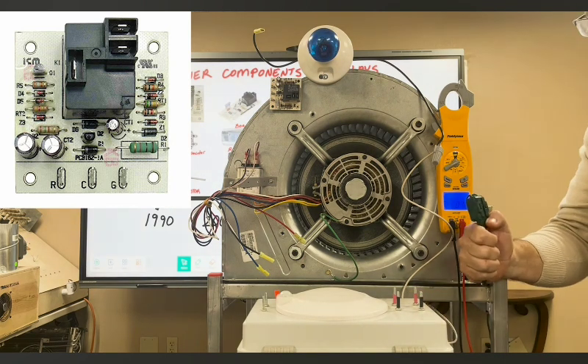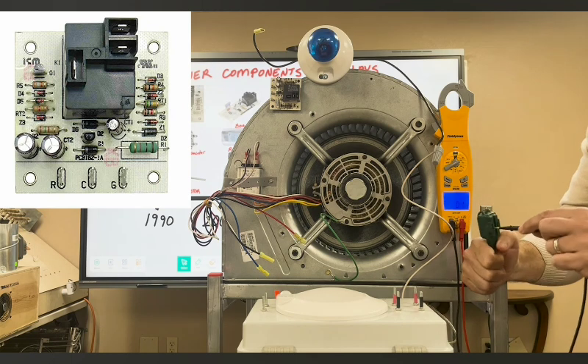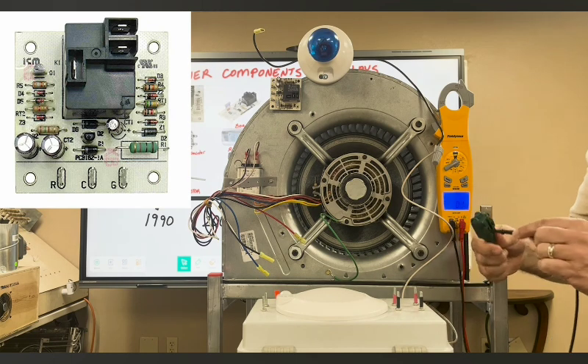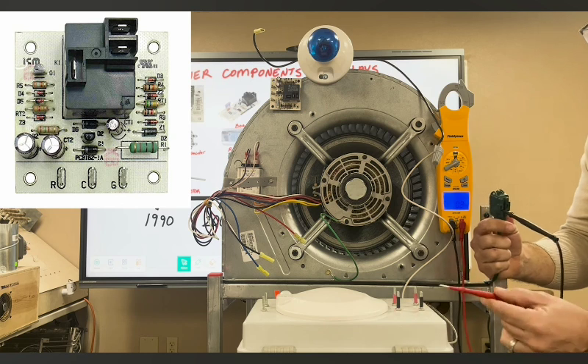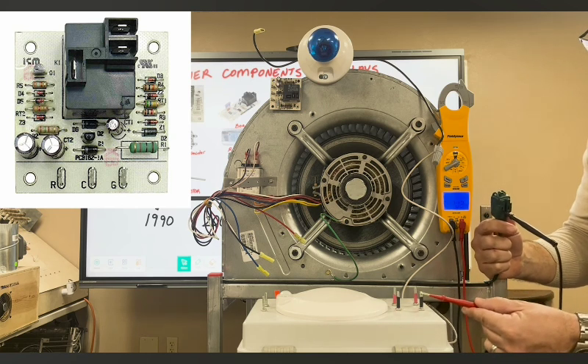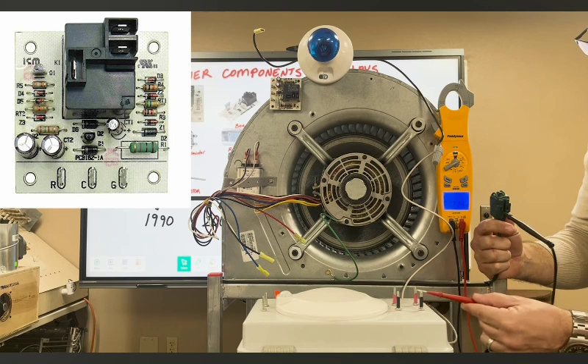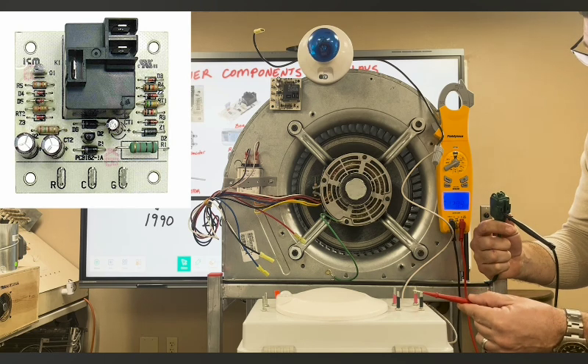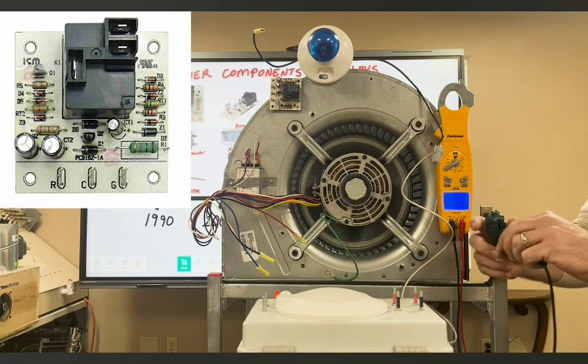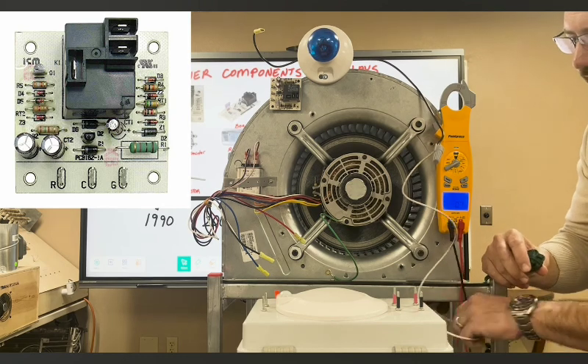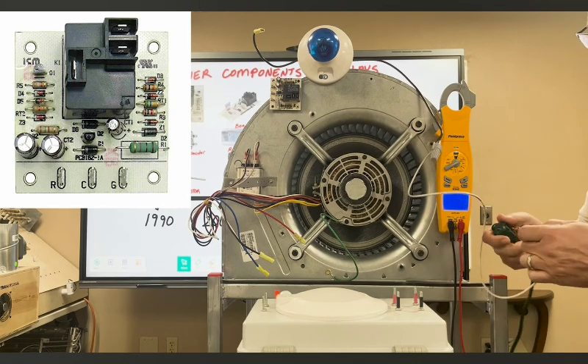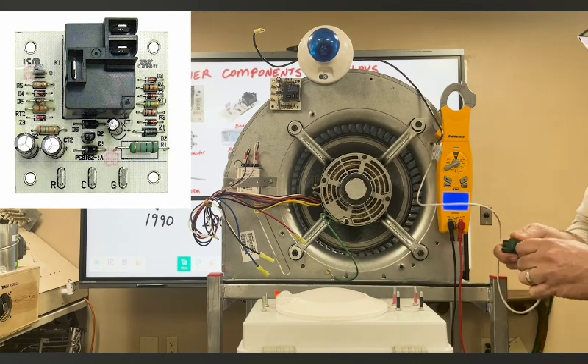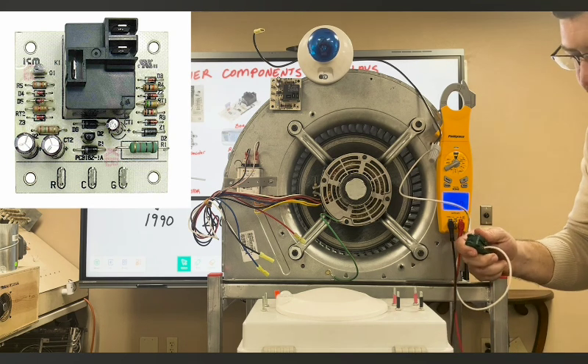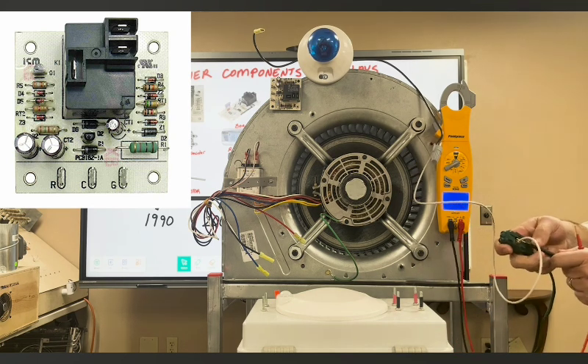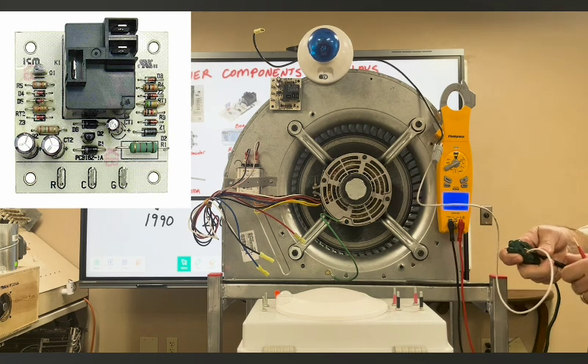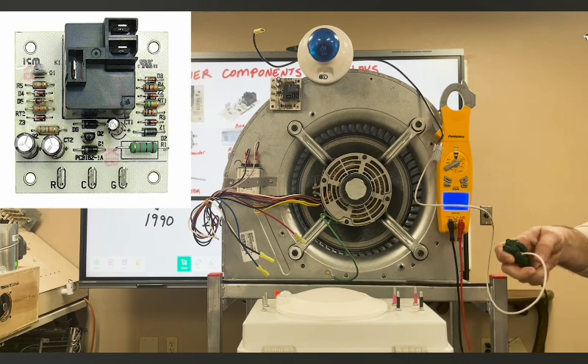I do have an extension cord here. This is to give me a neutral. I'm going to stick one of my test leads inside here, and I'm going to go between each leg. You should read 120 volts per leg. That's where we're getting our 240 from. The reason I have this extension cord here is because I'm going to take this white wire and plug it in to give me a neutral. I'm going to test that out. And we have a good connection.